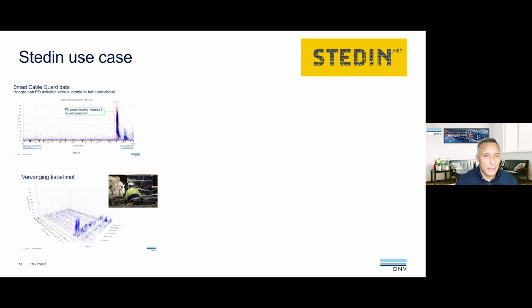They replaced this joint, and what we saw in our system was that once the joint was replaced, the partial discharge disappeared on that cable. So we knew that the joint was actually the cause of that problem.